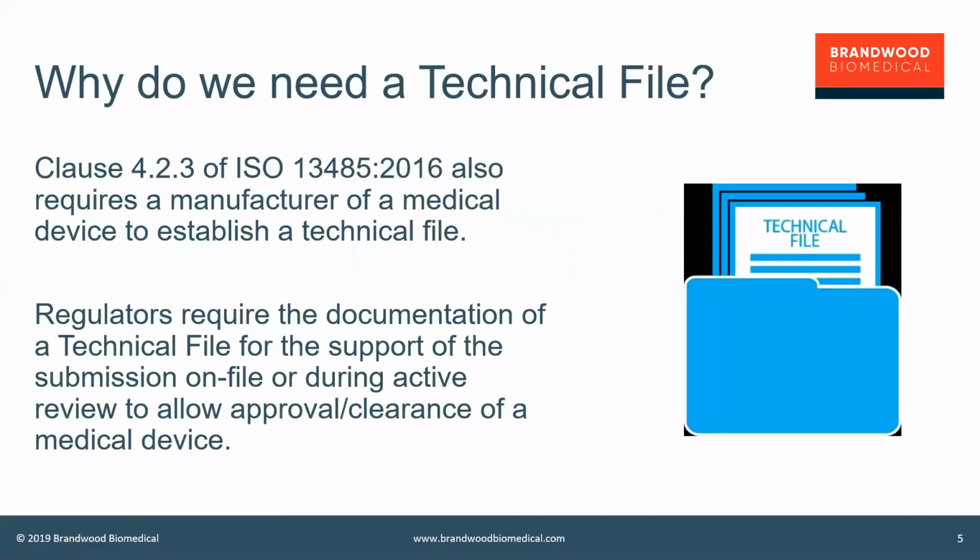And that goes into the next point. Why do we need the technical file? Well, simply, ISO 13485 suggests that you absolutely need to establish a technical file for your medical device. And in addition, and this is no surprise to anyone out there, regulators require the documentation within the technical file for submissions, whether it resides on file for future review in lower classification devices, or it's something that needs to be presented as part of an active review for those higher classification devices.